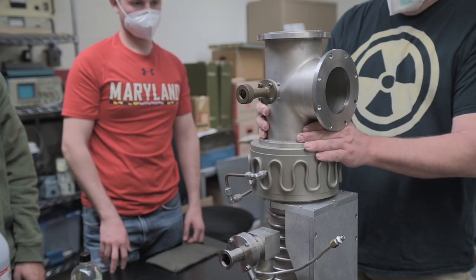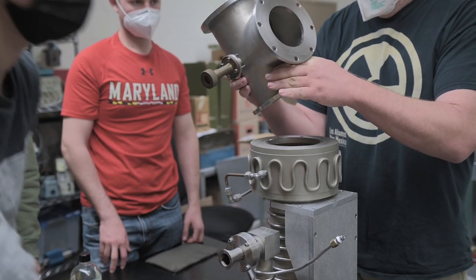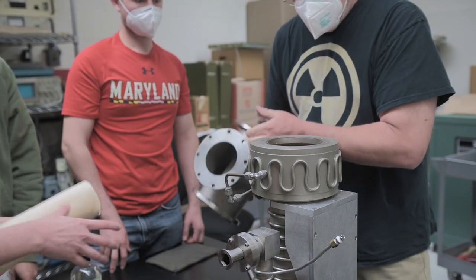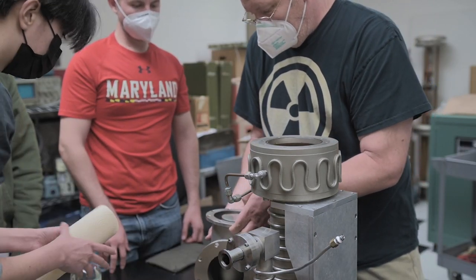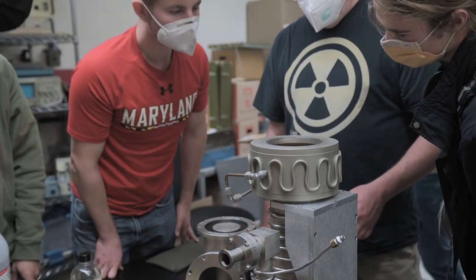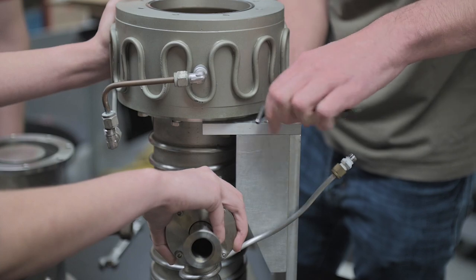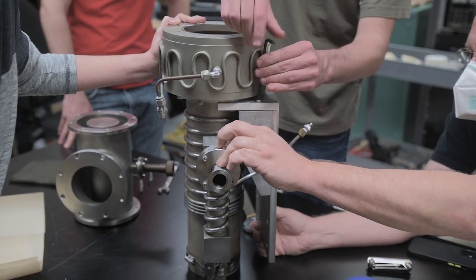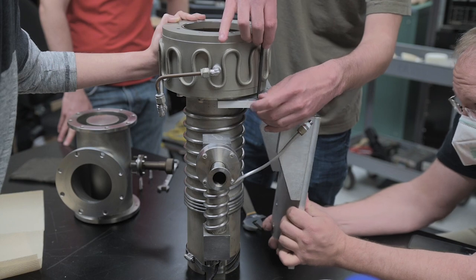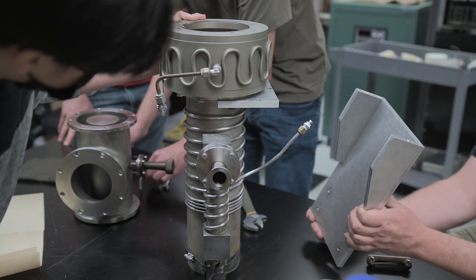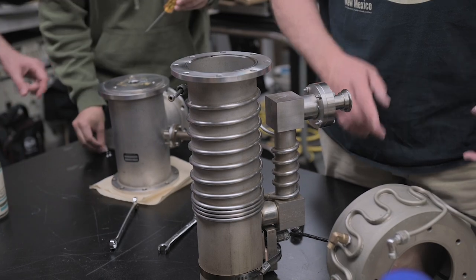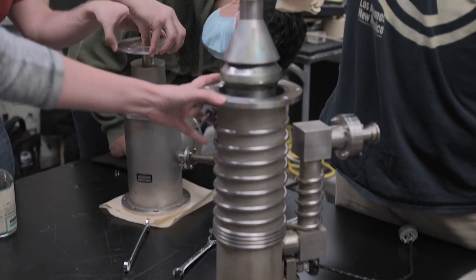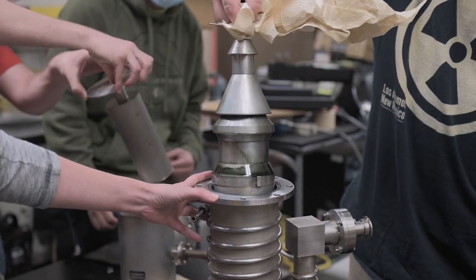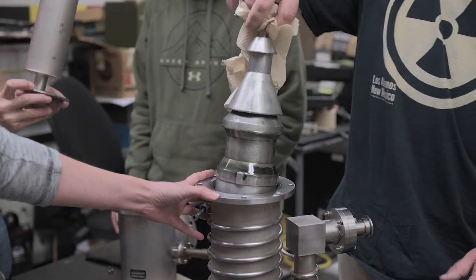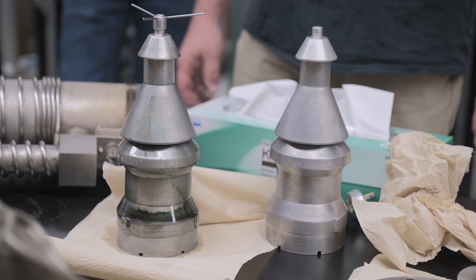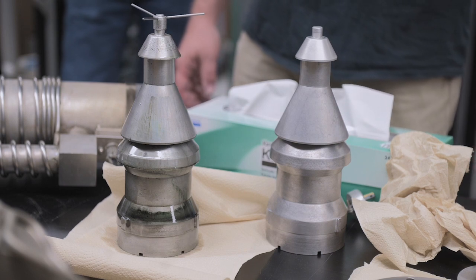Here you can see the cold trap being unbolted from the top of the diffusion pump. Now the diffusion pump is being removed from the frame which suspends it, so that the top of the diffusion pump with the water-cooled baffle can be removed, and out comes the Christmas tree. At the base of the Christmas tree you can see that black carbonized diffusion pump oil. To the right, you can see a brand new, clean Christmas tree.